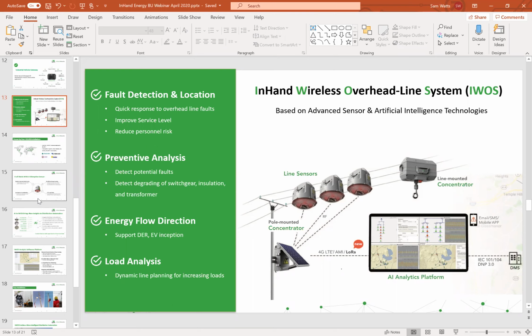They collect and use line harvesting for their power. As I'll get into, they only require 1 amp of power for line harvest at full function mode, which leads globally by several amps versus all the other sensor competition out there. So it's very important in long line, little load, not a lot of customers type situations, or just being able to use the sensors in a wide variety of applications and locations along the grid.